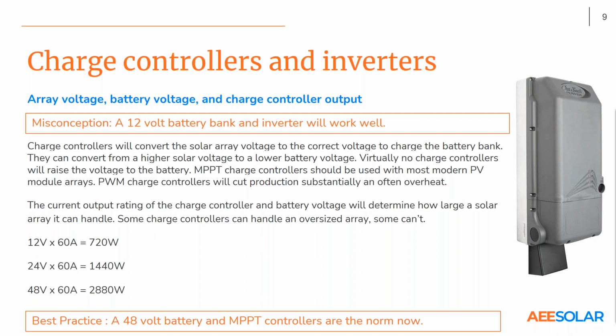A lot of charge controllers now will take even higher voltage input, so you can reduce your wire size and increase your string length. So you don't want to use an inexpensive PWM type charge controller, even a good one, when you're using any of the modern solar modules.